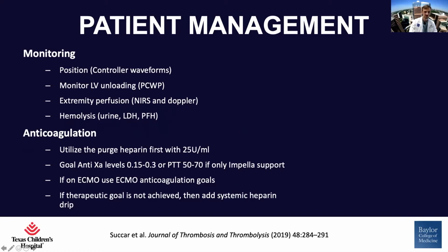The device requires its own anticoagulation. Some of the anticoagulation is provided through a purge fluid through utilization of heparin. Typically, it's started at 25 units per ml, and obviously the purge regulates the amount of heparin that goes into the patient. Typically, it's a very small fluctuation in the delivery of heparin, but requires fairly close monitoring. The literature sort of describes anticoagulation goals. Here at TCH, we use 0.15 to 0.3.